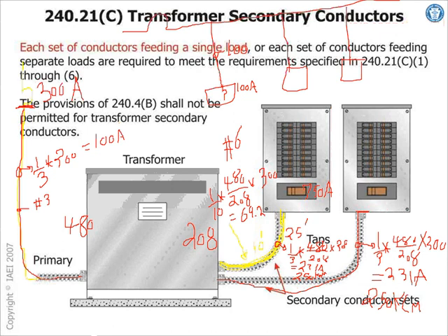So they give you a lot of leeway. So can you guys see? I can go from this transformer 25 feet if I size my conductor to 250 kcm. Now, if I want to go 25 feet in an industrial supervised location, no limitation, no overcurrent protection device, no minimum. It's 25 feet, but that conductor doesn't have to be even 250.